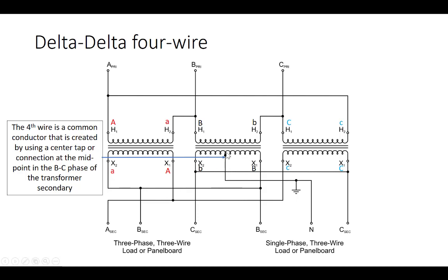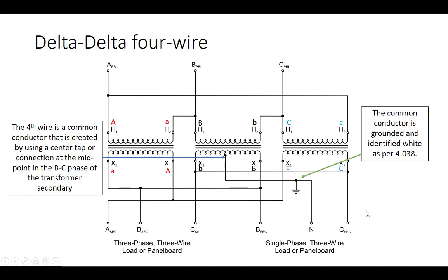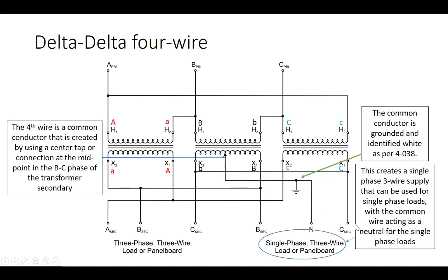Then, on the B to C phase, a tap is made at the midpoint of that winding, which gives us a common conductor for our single-phase system. And our single-phase system consists of line B, line C, and this common conductor. And this creates a single-phase 3-wire supply that can be used for single-phase loads, with the common wire acting as the neutral.